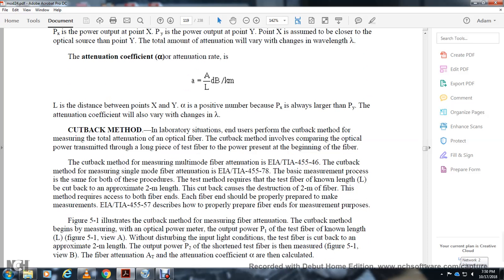The cutback method is used to measure the total attenuation of an optical fiber. It involves comparing the optical power transmitted through a long test fiber to the power present at the beginning of the fiber. EIA/TIA-455-46 covers the cutback method for multimode fiber, and EIA/TIA-455-78 covers the cutback method for single-mode fiber. Both procedures require cutting the fiber to a 2-meter length, which is destructive to that portion of fiber. EIA/TIA-455-57 describes how to properly prepare the fiber for measurement.